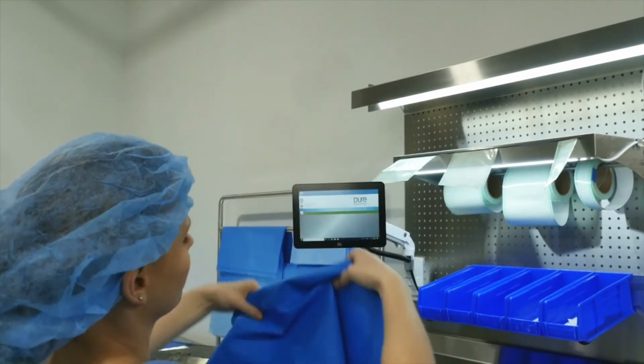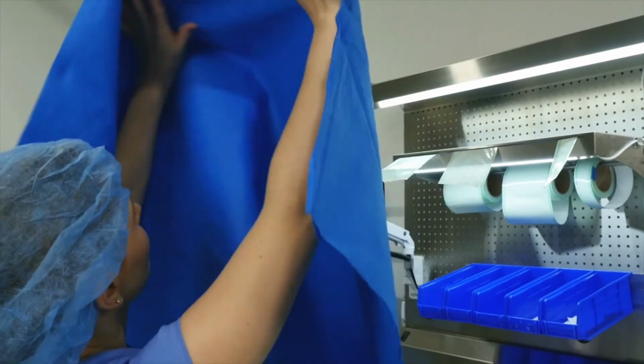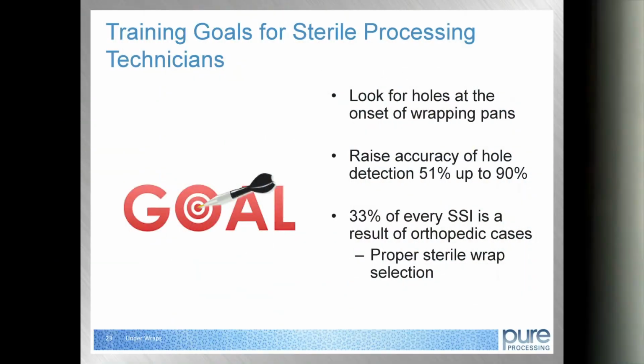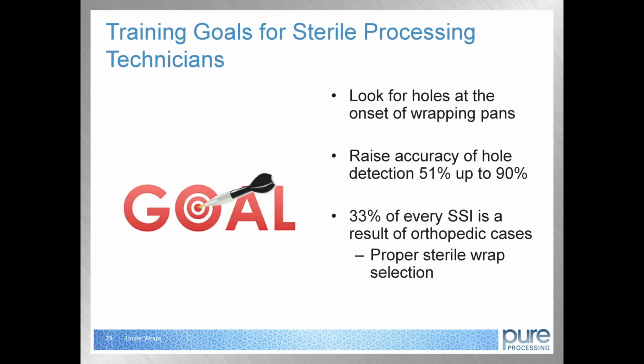Sterile processing, what we can do on that side is, when you're wrapping the pan, be able to detect any defects or holes right from the beginning, right at the start of when we're getting ready to wrap that pan. When I was in sterile processing working at my workstation, I would take a 48 by 48 wrap, lay it on my workstation, put the towels in there, wrap the pan, do everything that was necessary, put the indicators in there, tape it, and get it ready to go. And if I could not see the white, the pink, the green, or the purple coming through after I wrapped the pan, as far as I was concerned, that pan was fine. The integrity of that wrap was good.